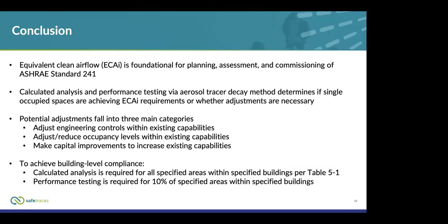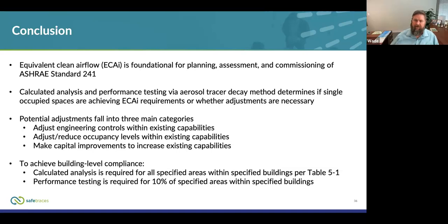Do you guys want to talk about resolving those types of differences and how to think about those, of what ultimately is considered passing? Do you have to pass both, or what happens if you're passing one but not the other? Yeah, so the calculator is intentionally conservative, right? And it's following exactly what is in the standard. So if you have a MERV 8 or a MERV 9 or a MERV 10 filter, you get 0 credit for it.